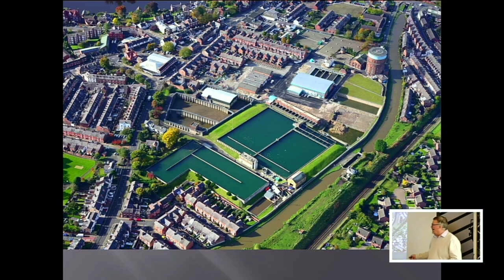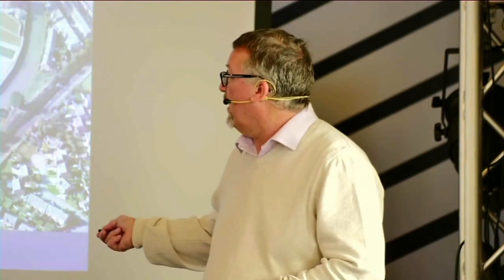These have to be emptied and drained out every 10 years for an intermediate inspection. You've probably heard of the Carsington Dam collapse. So even domestic reservoirs fall under regulation. A specialist panel engineer nominated by the government has to come in and they inspect every panel, casting, mark, everything, all the pumps, drain down procedures, overflows. They'll check everything on those reservoirs to make sure structurally we're not posing a danger to people living around the works itself.